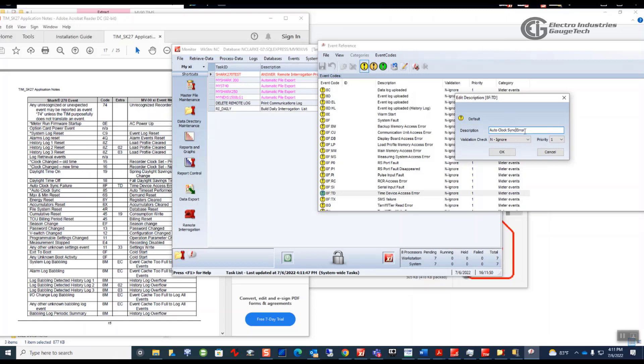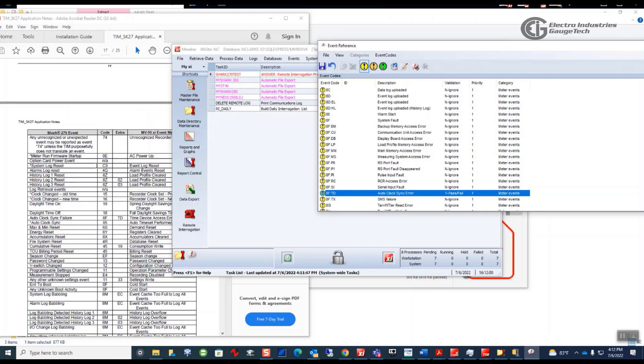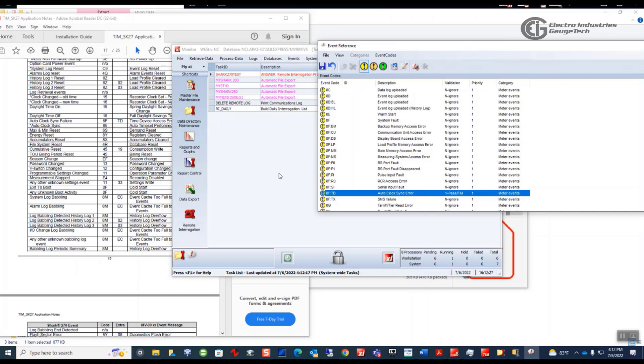I can edit this line and put 'auto clock sync error' as the description, then set it to 'yes' for pass/fail. I've now updated the event reference to match what the Shark 270 actually reports. Keep in mind that if you're using meters from different manufacturers, code 8F could mean something else — you have to make sure you're consistent per meter type. For EIG meters this won't be a problem since all our EIG meters are set up the same way.